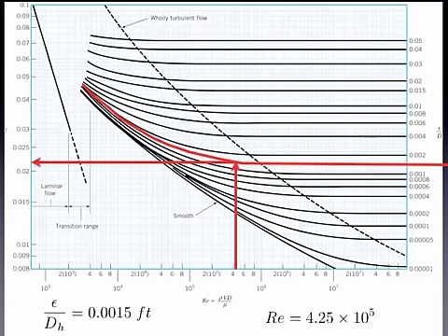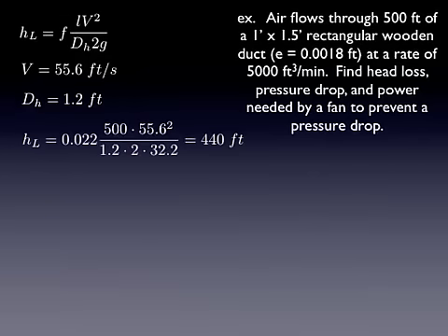Read across. That gives us a friction factor of 0.022, it looks like to me. Okay, we plug that into Darcy-Weisbach and we get a head loss of 440 feet.